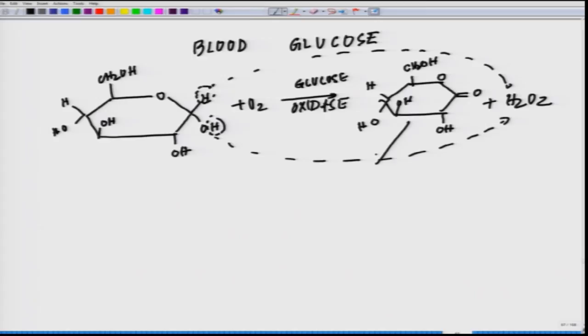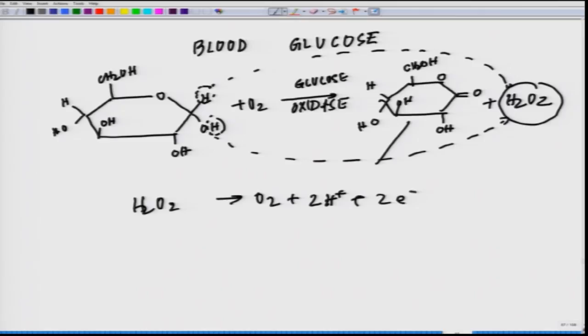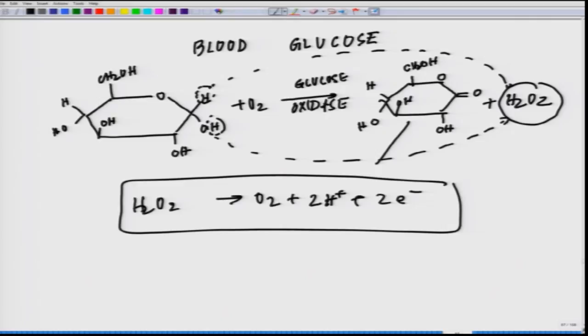The early glucose monitor measured the H2O2 by oxidation at a single working electrode held at +0.6 V versus Ag/AgCl. The reaction at working electrode is: H2O2 → O2 + 2H+ + 2e−. The current is proportional to the concentration of H2O2, which in turn is proportional to the glucose concentration in the blood.